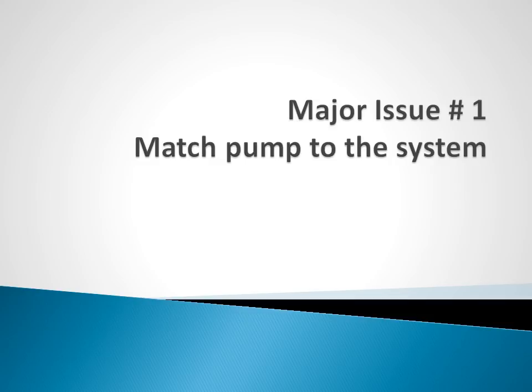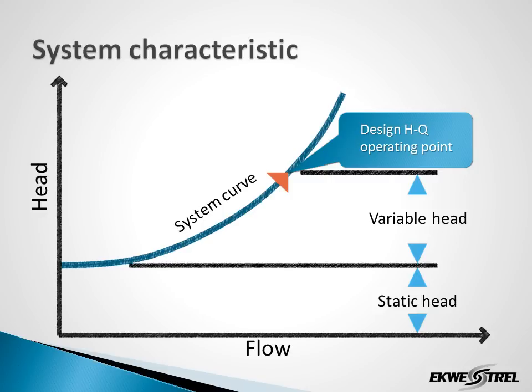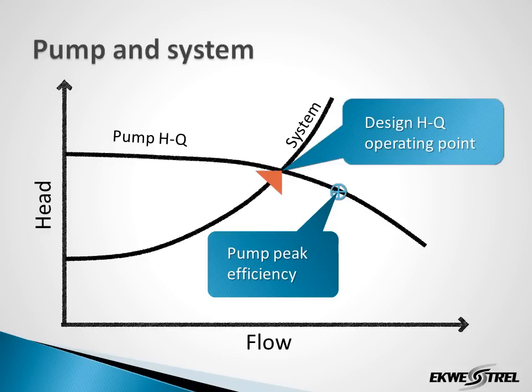We're going to take a closer look at major issue number one: matching the pump to the system. The conditions of service necessarily begin with an estimate of the system head versus flow, or system curve. System curves will always have a variable head component, and many — but not all — will have a static head component as well. A pump will only operate on the system characteristic curve. Here we have the pump curve and here's the system curve, and this is where the pump will operate. In this particular case, the pump peak efficiency is to the right at a higher flow relative to where the pump is operating, so this pump is slightly oversized.